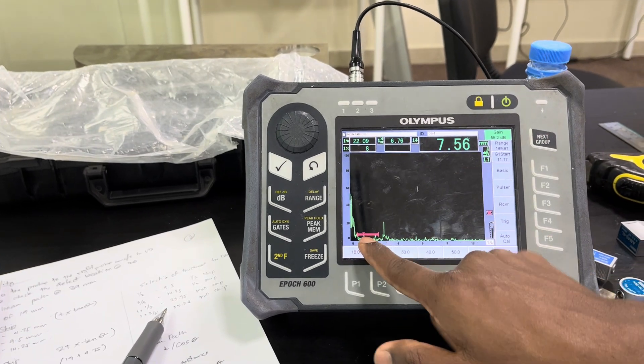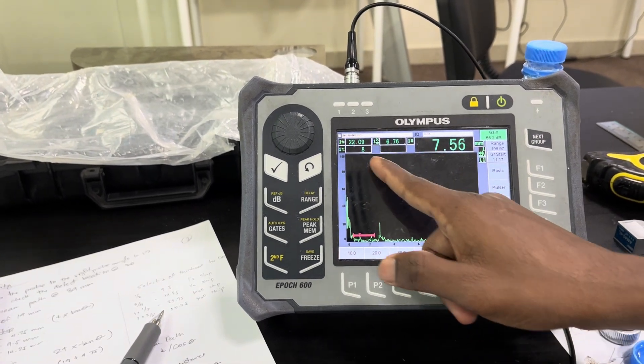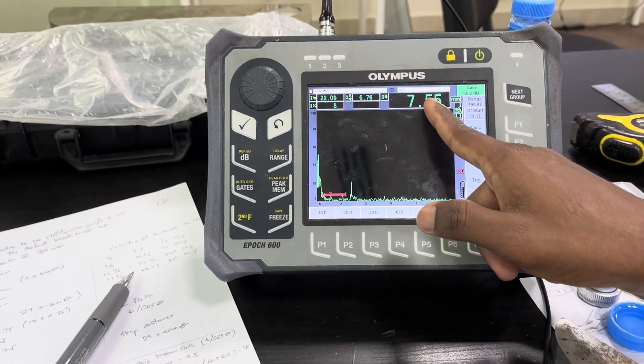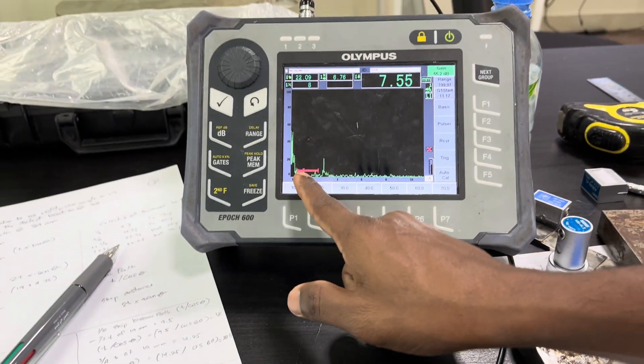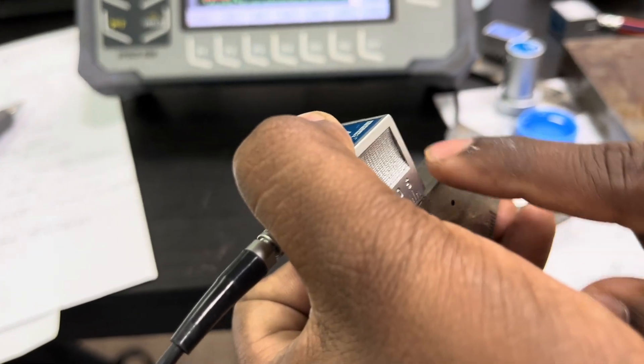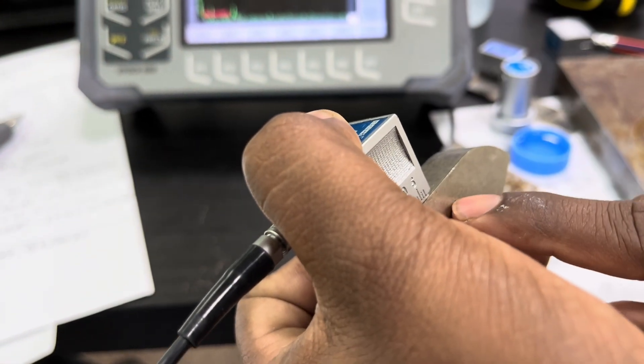This is the defect echo. Now we can see the depth here: 7.5mm is exactly the distance from the center of the hole to the surface—7.5mm depth.